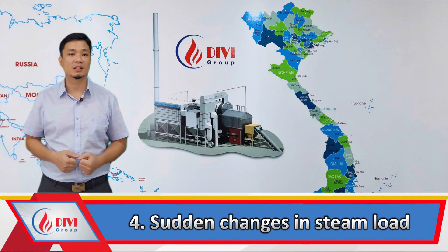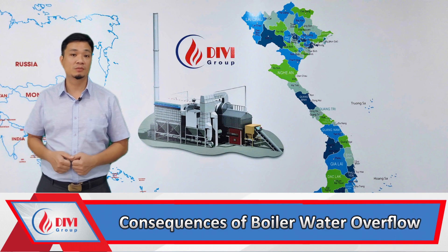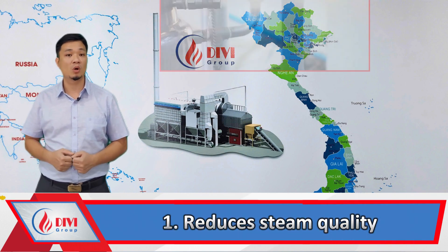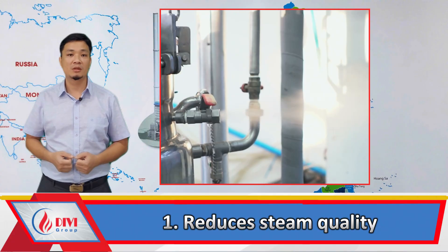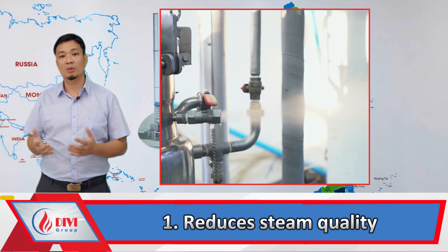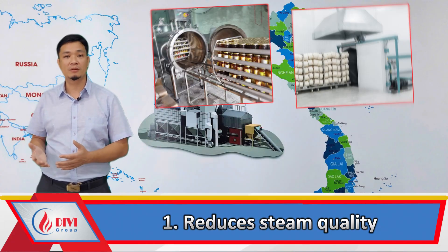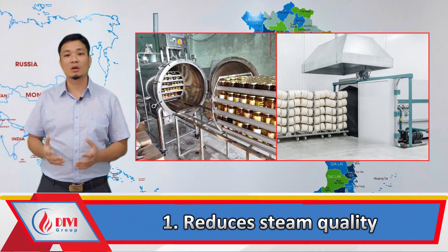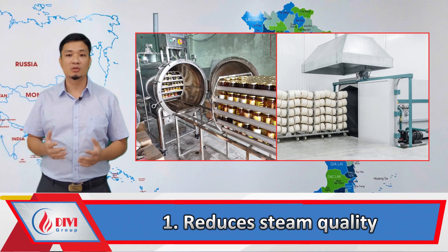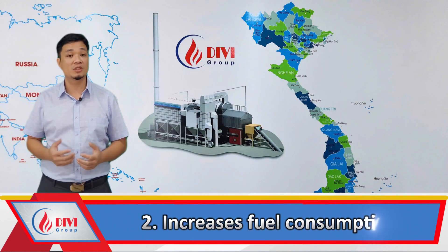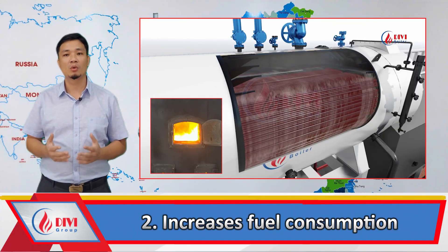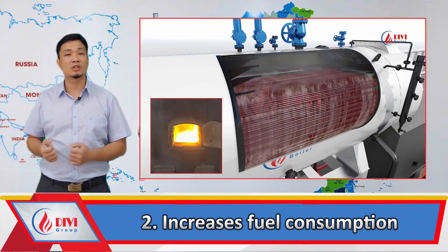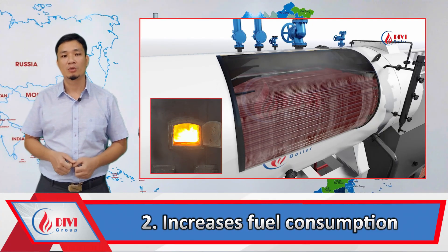Consequences of boiler water overflow. First, reduced steam quality: when water overflows into the steam lines, the steam produced contains more moisture, which affects equipment that uses steam in the production process, such as dryers and autoclaves. Second, increased fuel consumption: excess water in the boiler requires more energy to boil, increasing fuel consumption without improving efficiency.